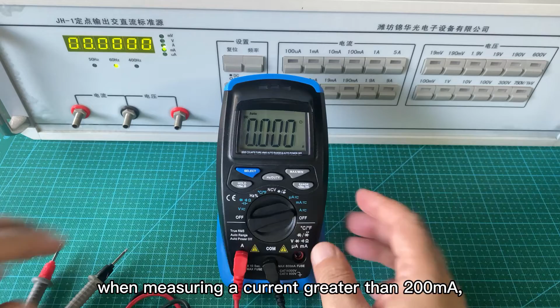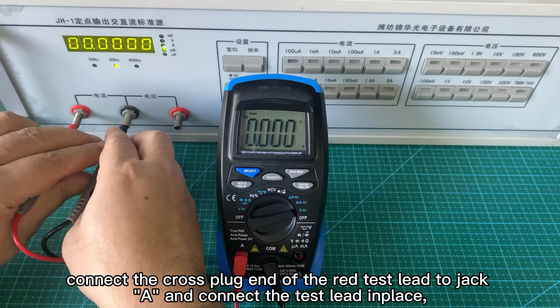Note: when measuring a current greater than 200 mA, connect the cross-plug end of the red test lead to the 10A jack, and connect the test lead in place, and then input the current test. Test DC current 5A.